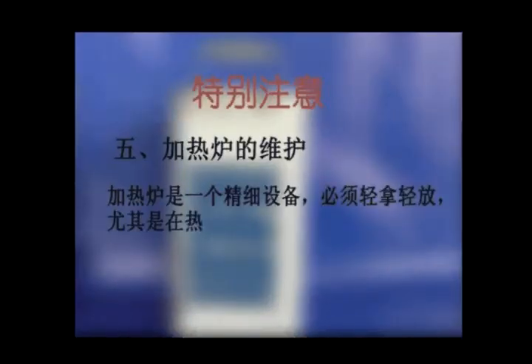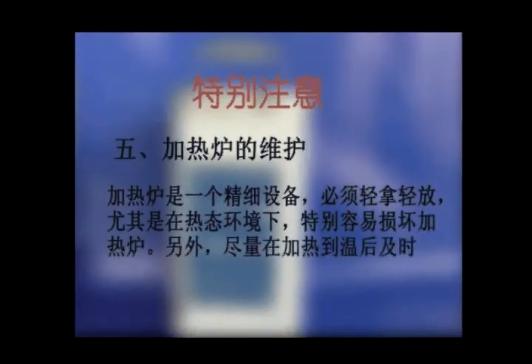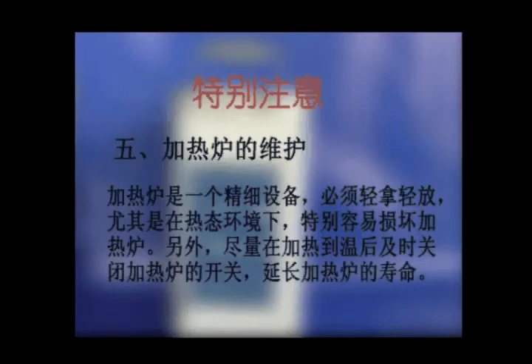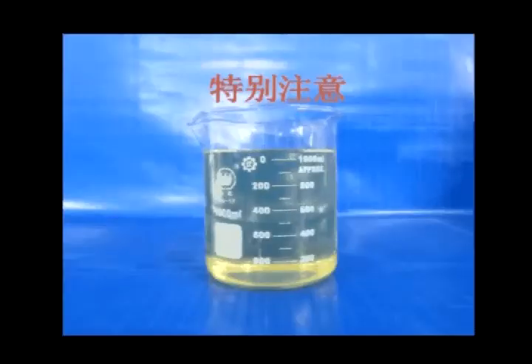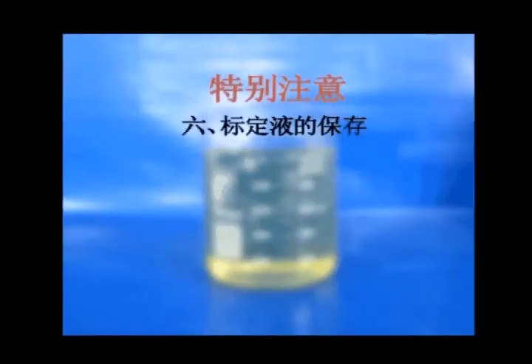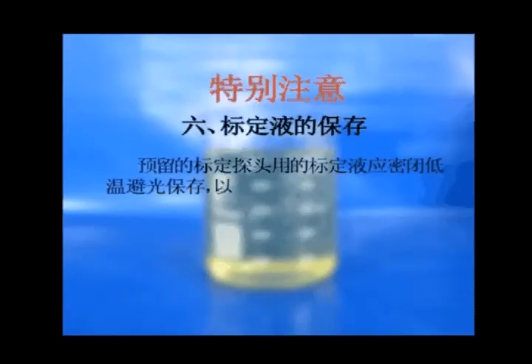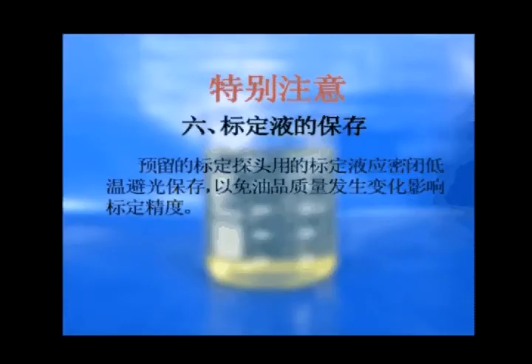Special remarks 5. The maintenance of the furnace. The furnace is precision equipment, so it needs especially careful handling. If not, the furnace is easily damaged. In addition, turn off the furnace in time when the temperature is suitable to increase the service life of the furnace. Special remarks 6. The conservation of the calibrated liquid. Reserved calibrated liquid used for probe calibration should be preserved in a closed, low temperature place away from light. Otherwise, the oil quality may change and the calibration will be inaccurate.